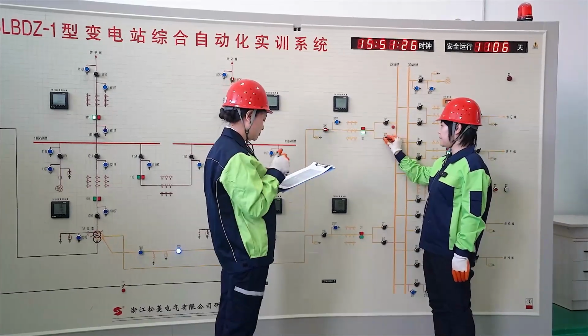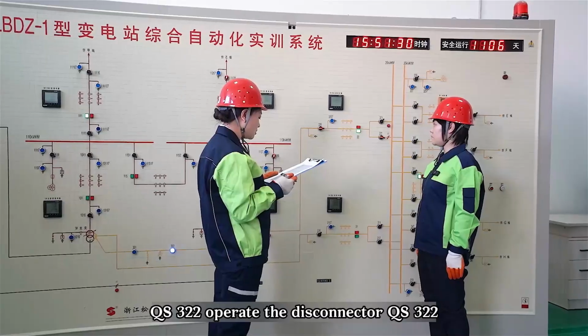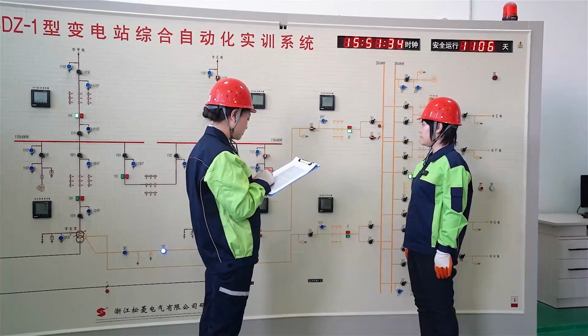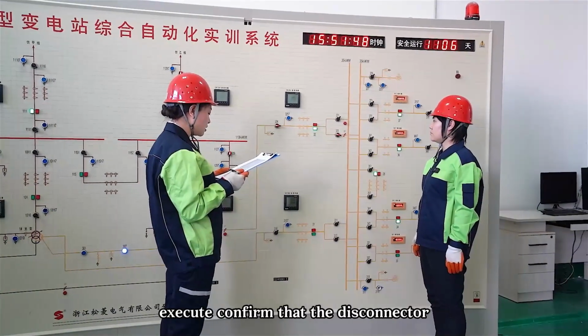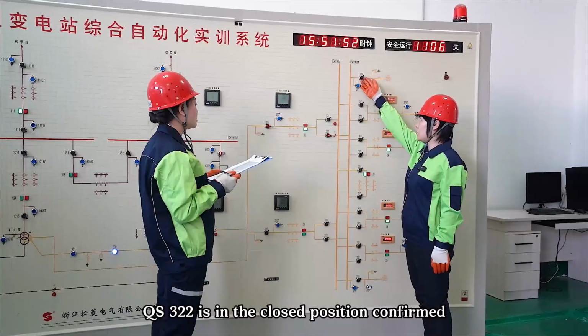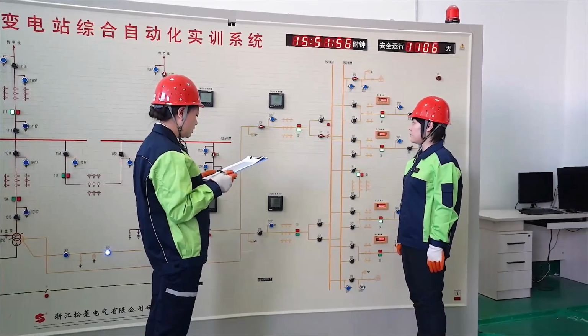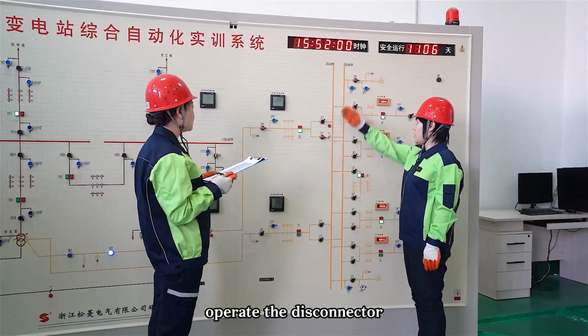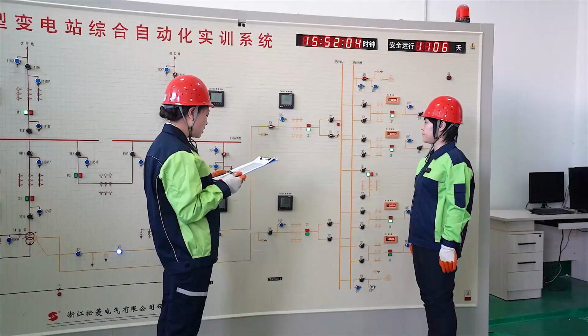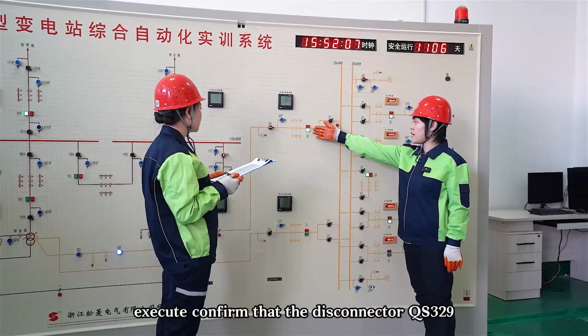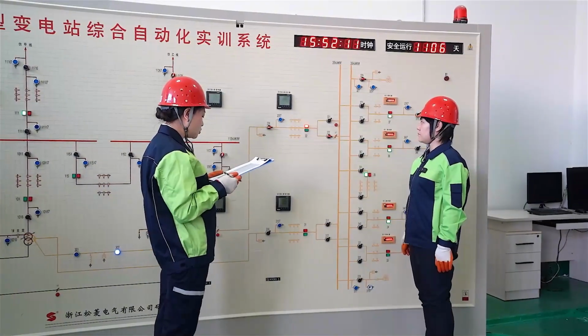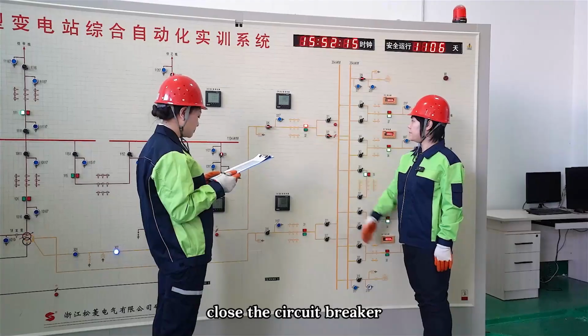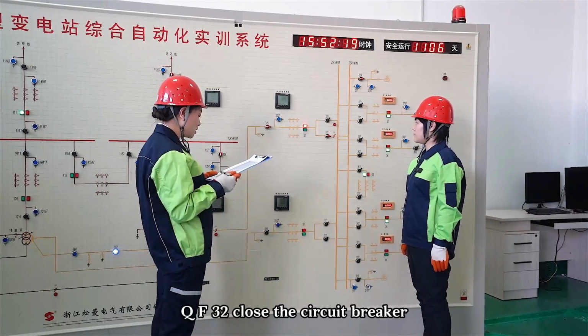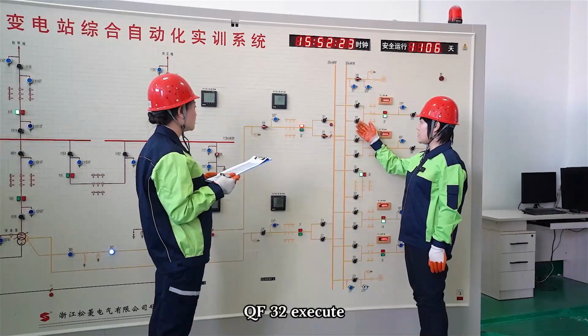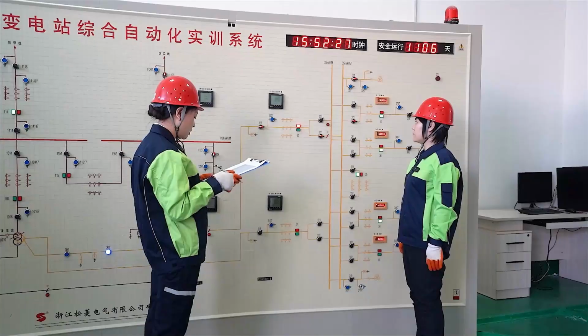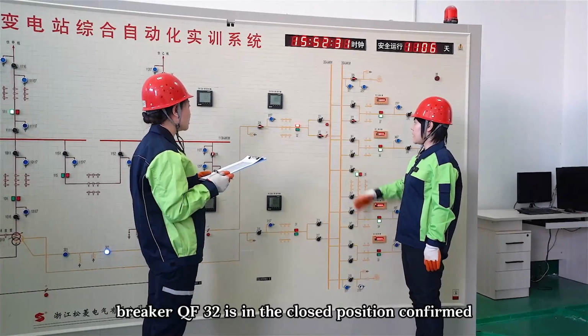the disconnector QS326 is in the closed position. Confirmed. Operate the disconnector QS322. Execute. Confirm that the disconnector QS322 is in the closed position. Confirmed. Operate the disconnector QS329. Execute. Confirm that the disconnector QS329 is in the closed position. Confirmed. Close the circuit breaker QF32. Execute. Confirm that the circuit breaker QF32 is in the closed position. Confirmed.